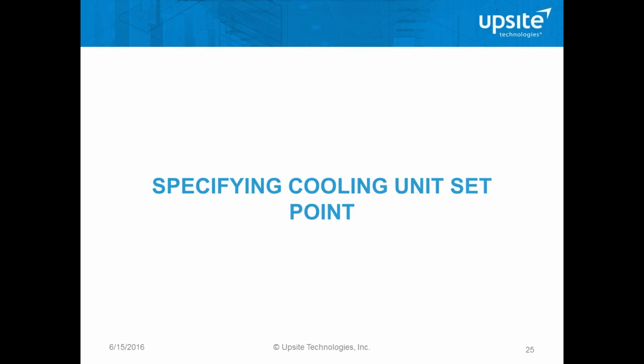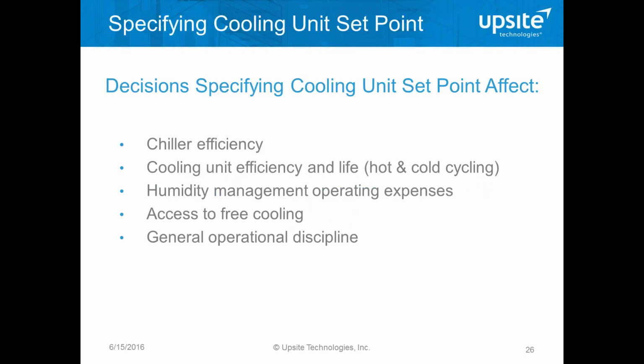Then does investing in tape storage or solid state storage actually allow us to not build a mechanical plant and to save those capital expenses and operating expenses? Cooling unit set point is a facilities function that is typically driven by our friends in the IT community, and so we look at that as well, and its effect on chiller efficiency, on cooling unit efficiency, and its effective life as well. If we're just running a cooling unit on all the time at some low level versus cycling it on and off or cycling hot and cold, we get a lot more life out of that equipment.